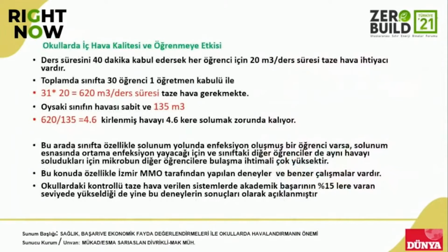And given the fact that each session is 40 minutes, that means at least 20 cubic meters for each student. That means 620 cubic meters is needed. However, the capacity is 135 cubic meters. That means students have to breathe this poor air 4.6 times during their classes. And we know that it creates certain problems.